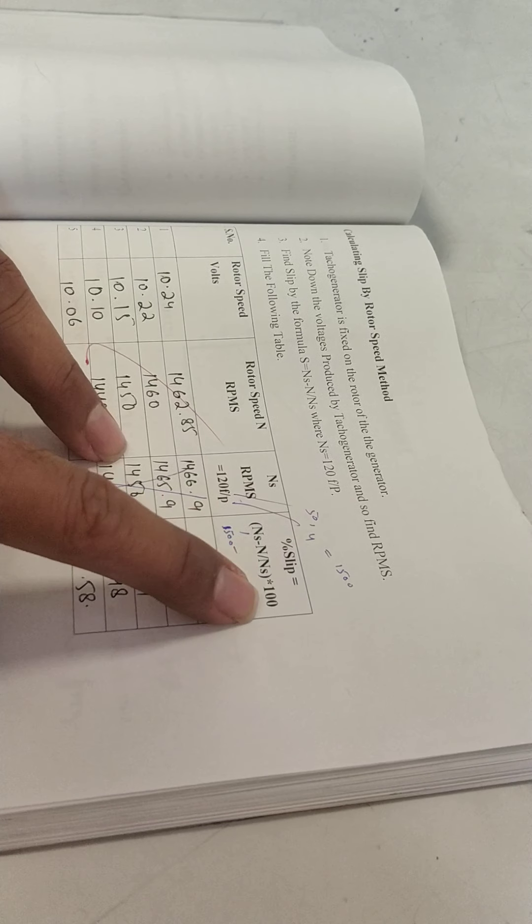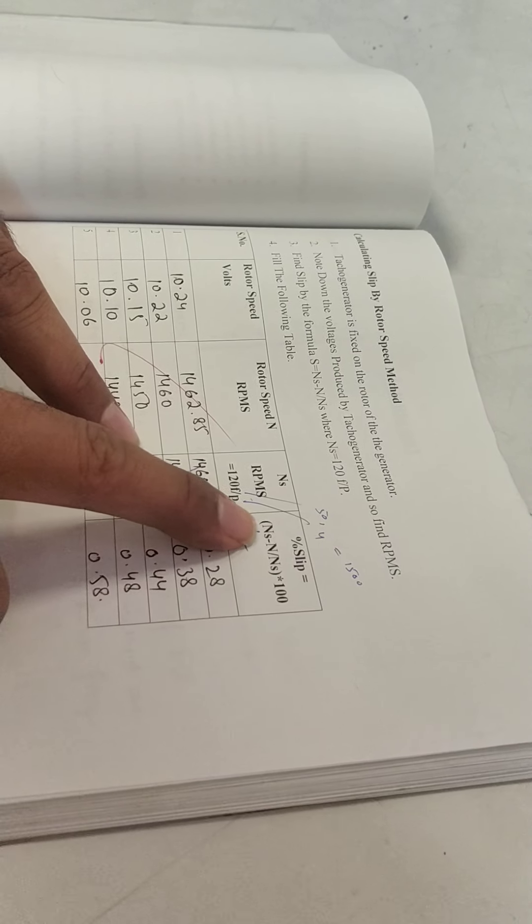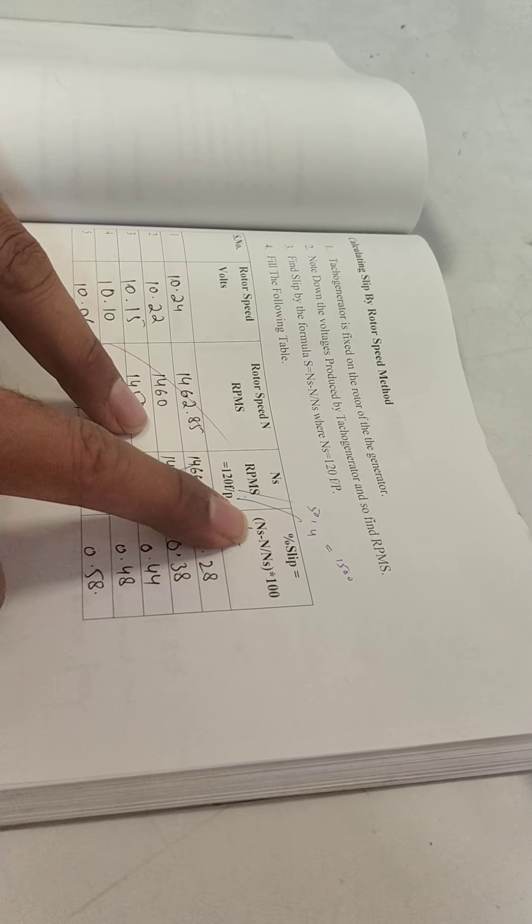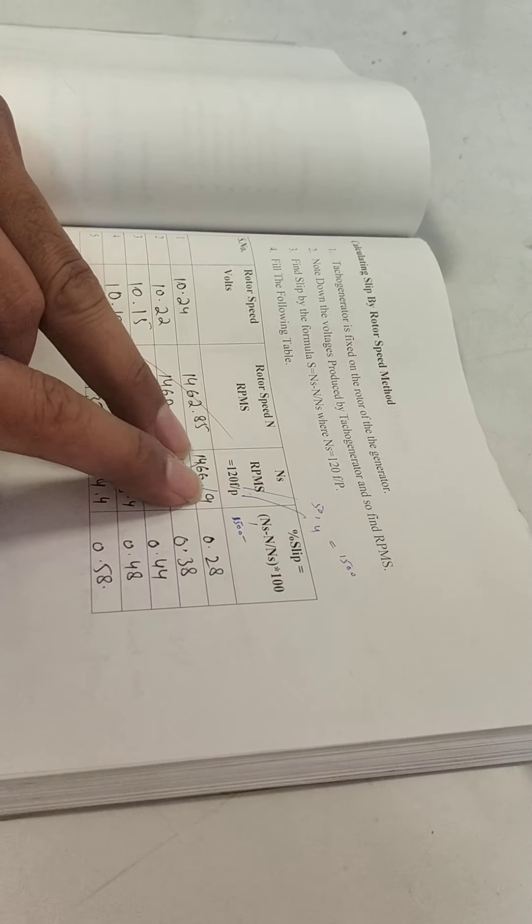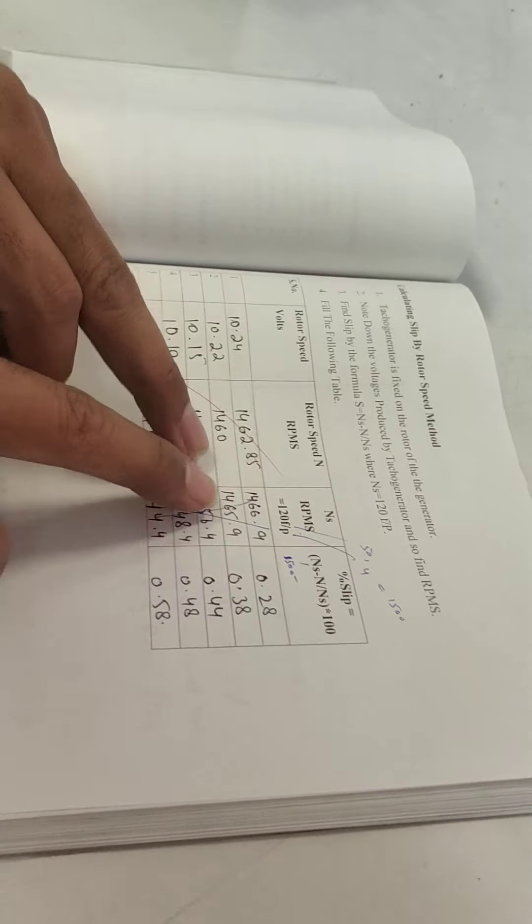We will change the load and then we will calculate the slip. So slip equals NS minus N over NS multiplied by 100. NS will be 1500 constant and we will calculate the relevant values. So this will be the percentage of the slip. This will be your method to find the slip of 3-phase slip ring induction motor by rotor speed method.